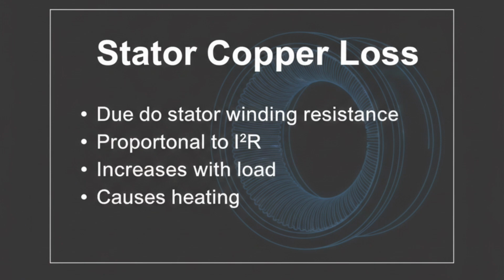Now we focus on stator copper loss. This loss occurs in the stator winding conductors because they have electrical resistance. Whenever current flows, power is dissipated as I²R loss. This means that if stator current doubles, copper loss becomes 4 times. Therefore, at higher load, stator copper loss increases sharply and becomes one of the dominant heating sources. In continuous duty motors, designers carefully select conductor size and insulation so that this loss remains within permissible limits.